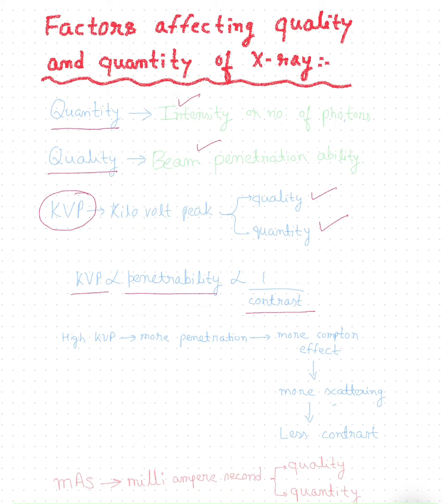Let's understand this concept. When we increase the KVP, it leads to more penetration of the patient by the X-ray beam. More penetration causes more Compton effect, which leads to more scattering of the X-ray beam. Finally, these scattered X-ray beams lead to reduced contrast of the final image.